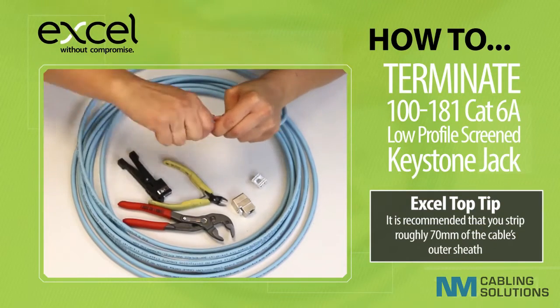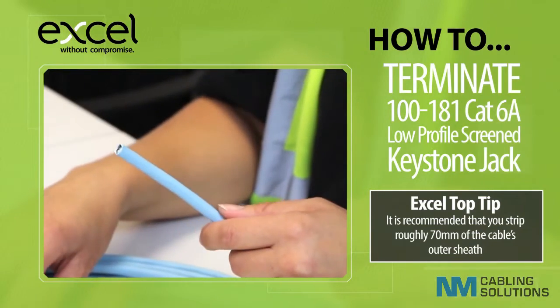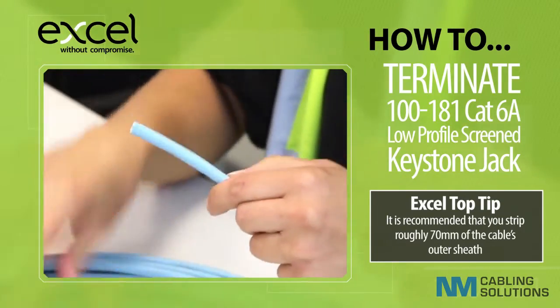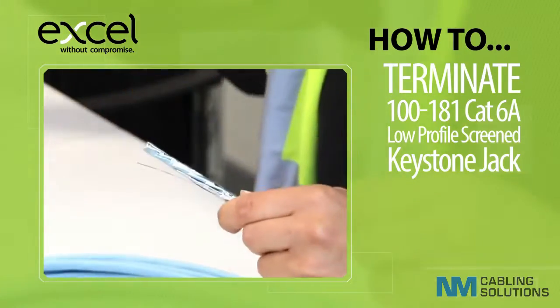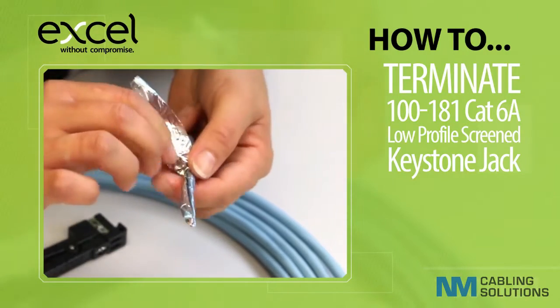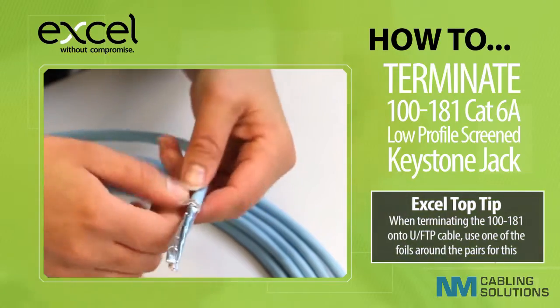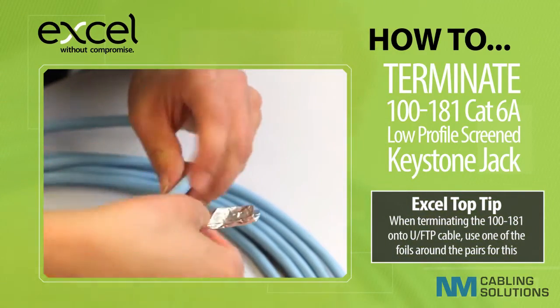Bend the cable to break the outer sheath away from the cable. We would recommend you strip off roughly 70mm of the cable's outer sheath. Take the foil layer of the cable and fold it back on itself in one piece. Fold the foil layer in half and wrap it around the cable sheath, exposing the shiny side.